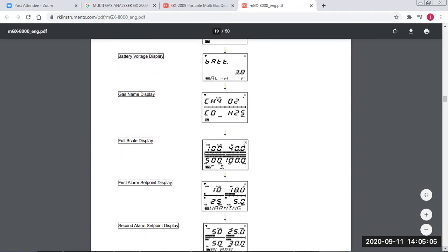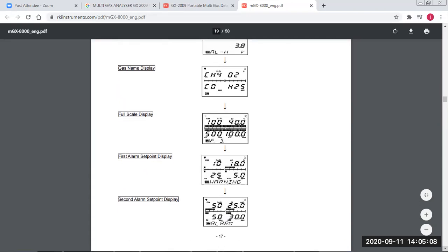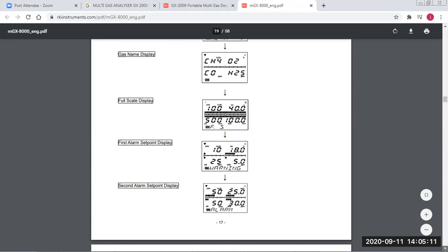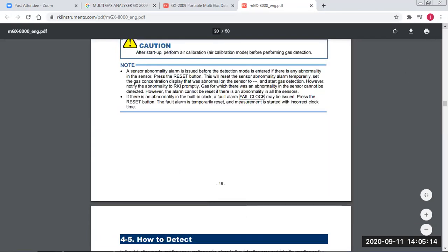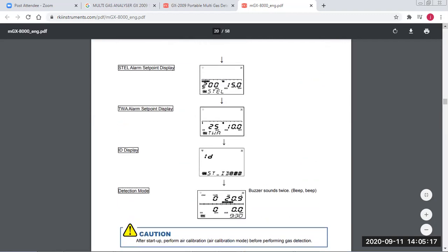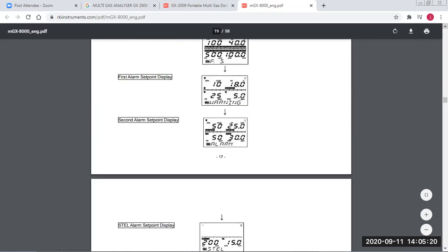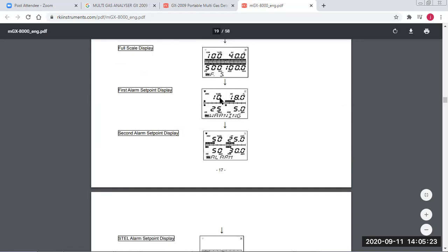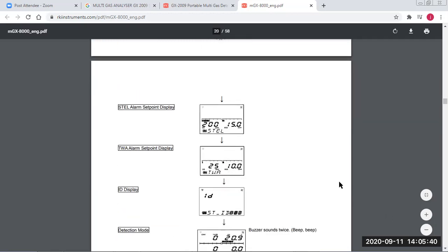Then full scale, the maximum gas which it can measure, and the first alarm set points, that is, at what level you will get the alarm. For hydrocarbon it will alarm at 10% LEL, for oxygen 18%, for carbon monoxide at 25 ppm, and for H2S at 5 ppm. The second alarm settings are also there. Then we have the TLV or STEL values fed in. For carbon monoxide it is 200 and for H2S it is 15. For oxygen and hydrocarbon, of course, we don't have them.